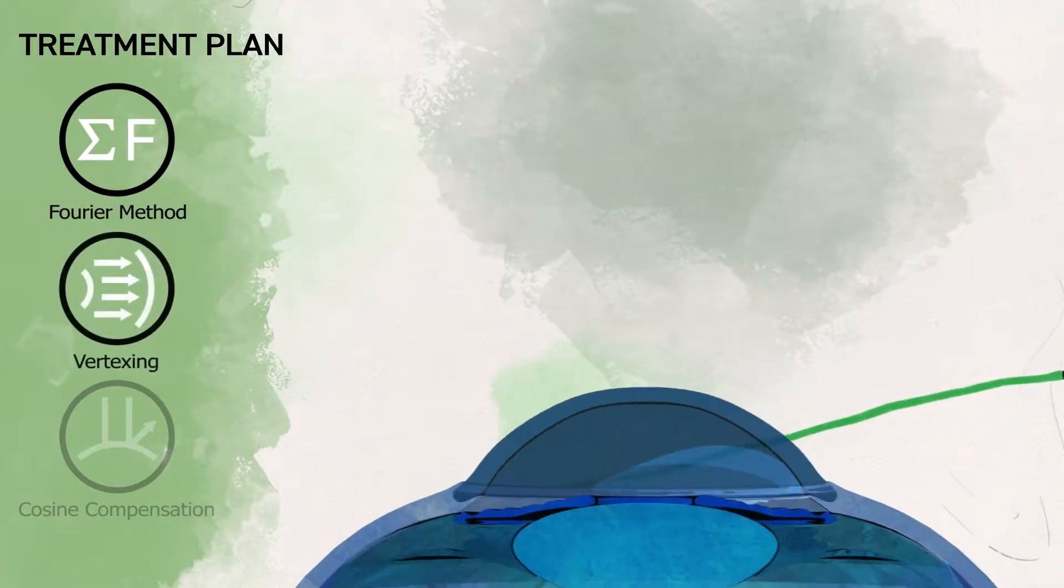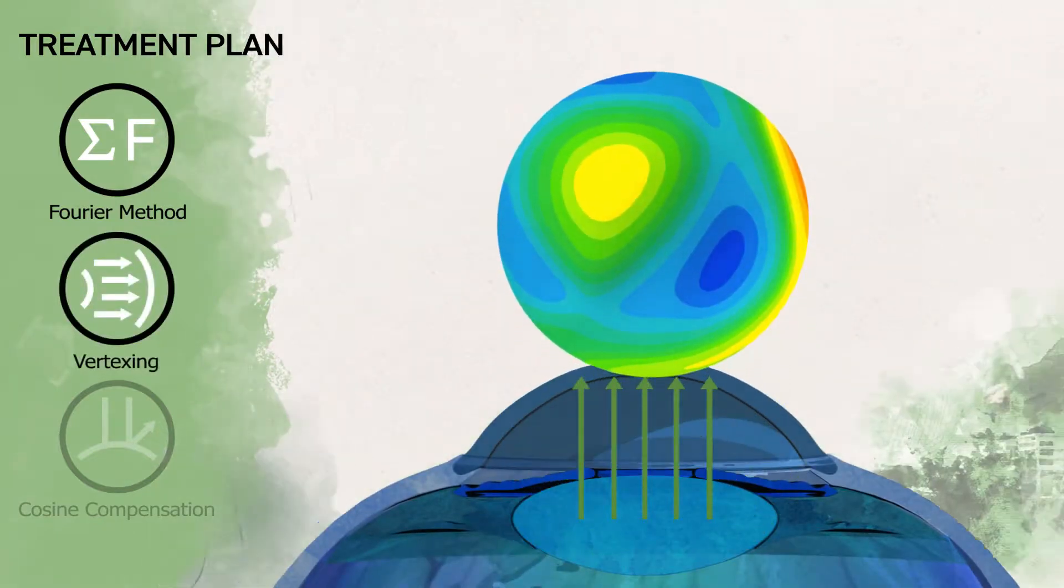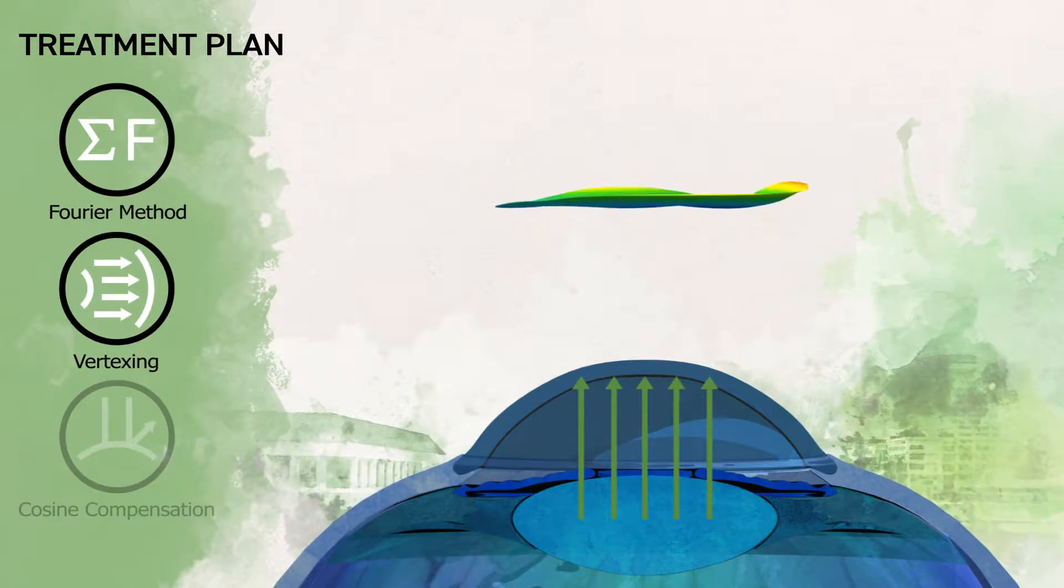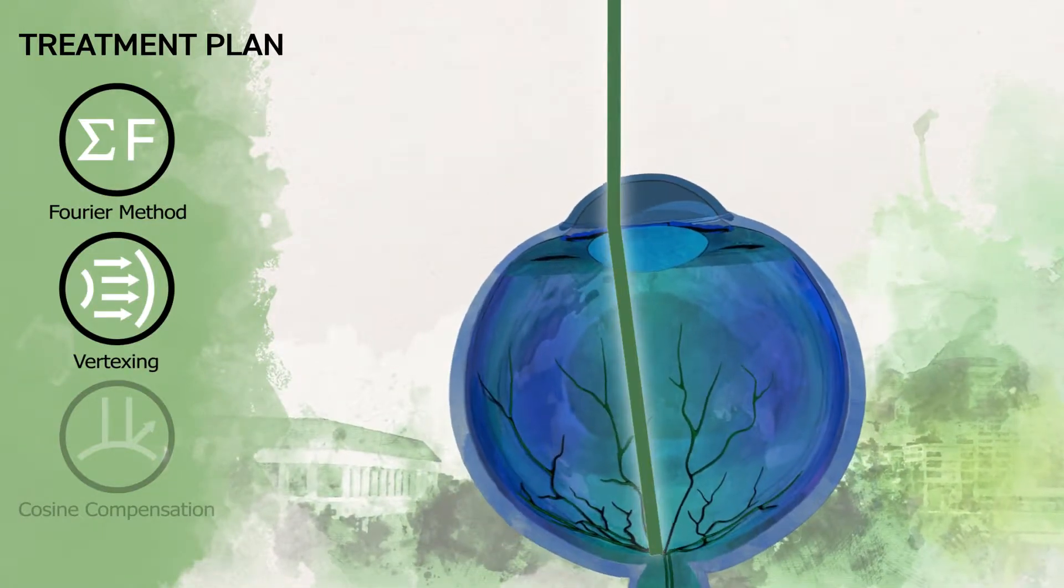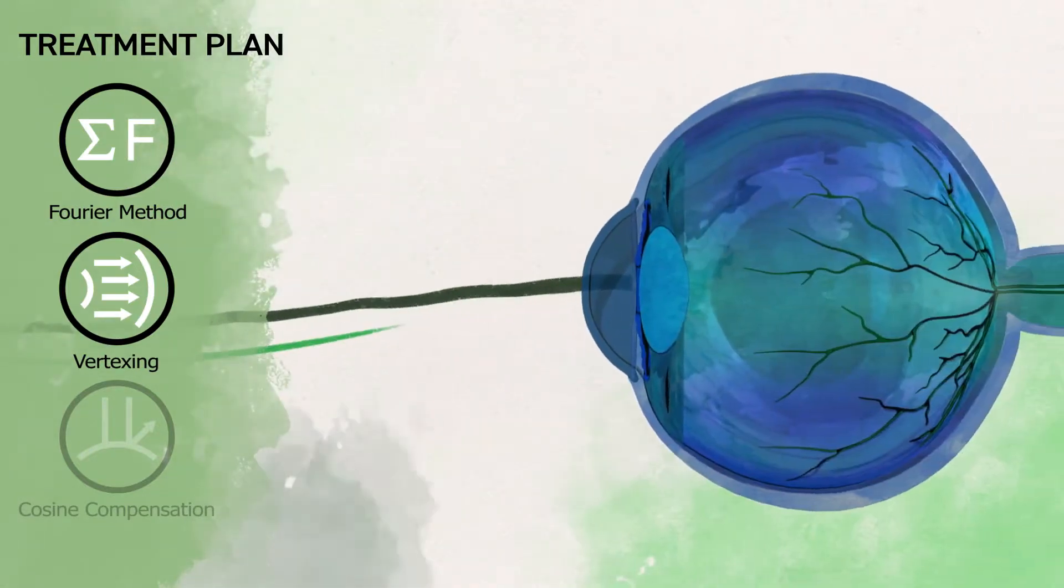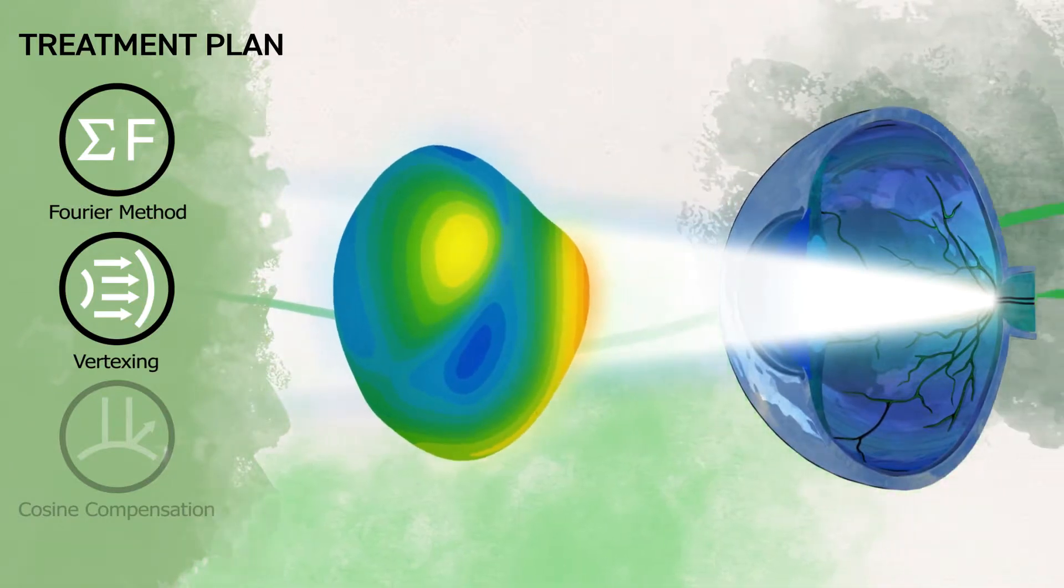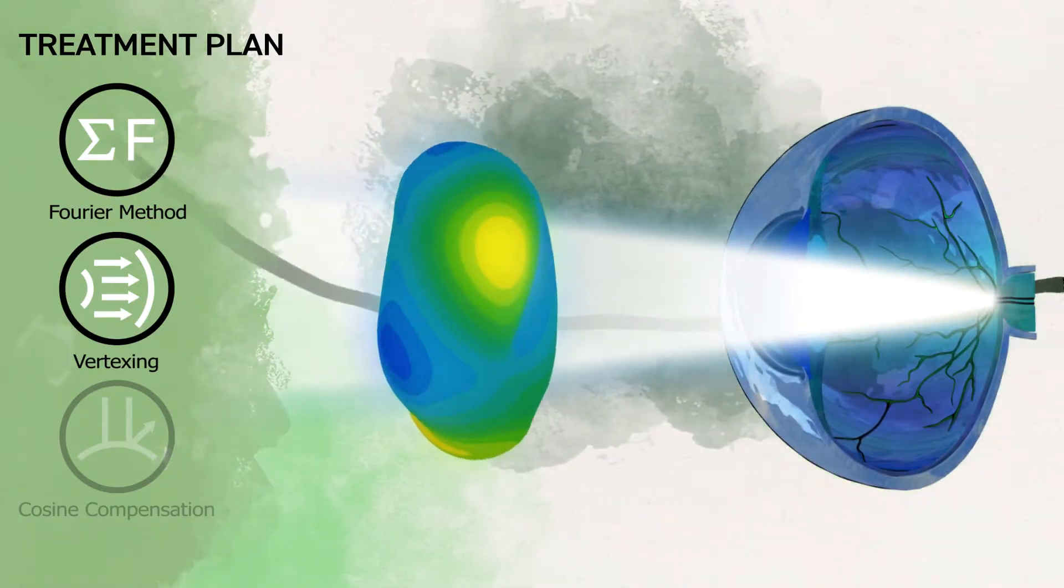Before ablation, the system translates the wavefront measurements from the pupil to corneal surface, considering the minuscule variations of the cornea and its unique combination of steep, flat, and tilt. This process, known as wavefront vertexing, uses the captured topography data instead of K values to create a treatment plan.